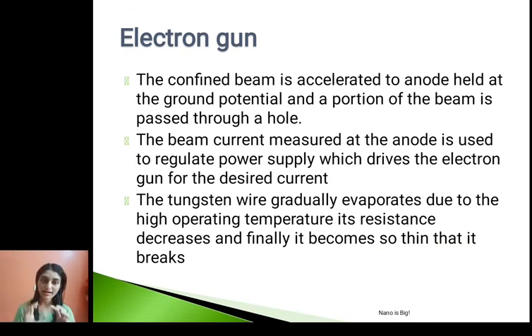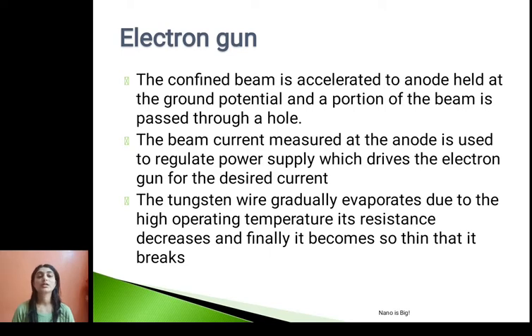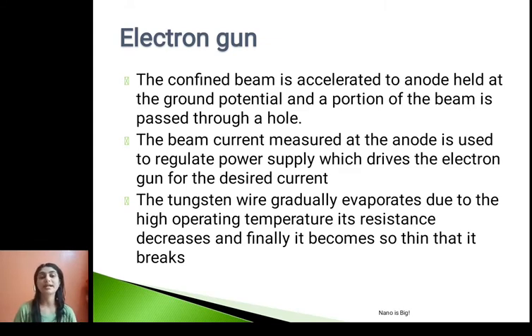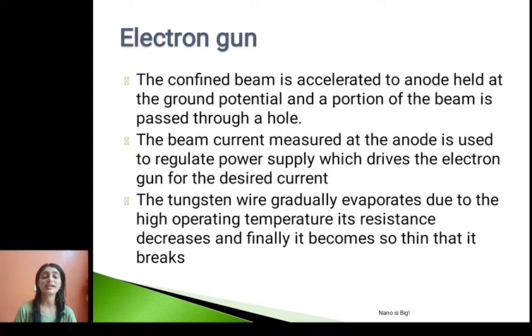The confined beam is then accelerated towards the anode, which is held at ground potential, and a portion of the beam is passed through a hole. The beam current measured at the anode is used to regulate the power supply which drives the electron gun at the desired current. The tungsten wire gradually evaporates due to the high operating temperature; its resistance decreases and finally it becomes so thin that it breaks.